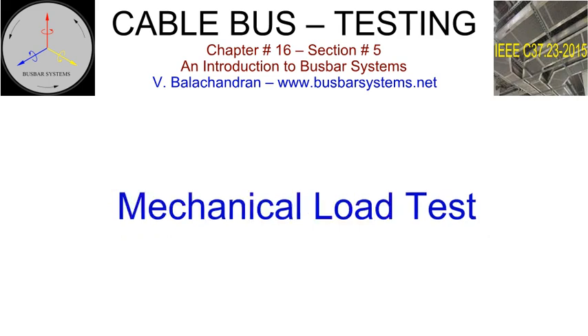Mechanical load test. A mechanical load test shall be carried out on a 20 feet long, fully assembled cable bus. The cable bus assembly shall be supported at the extreme ends. A load equal to the weight of one section, complete with support blocks and cable, plus 90 kilograms, shall be placed in the middle of the span supported at either end for 5 minutes. Its deflection is monitored. There should not be any appreciable deformation.